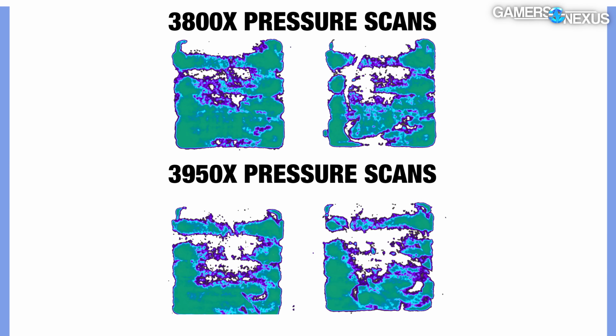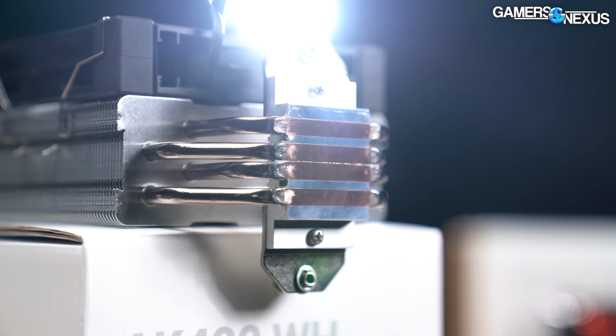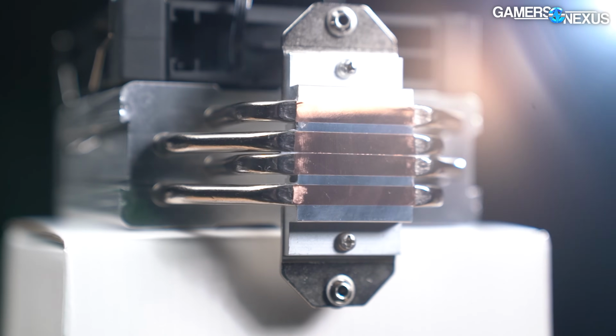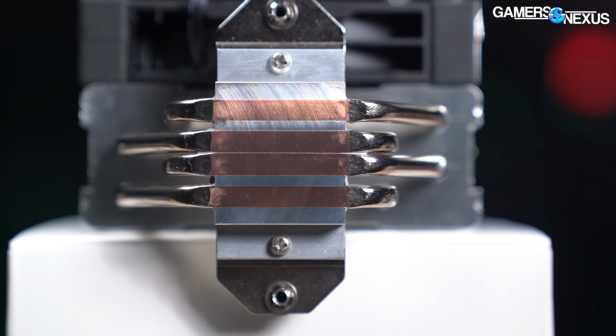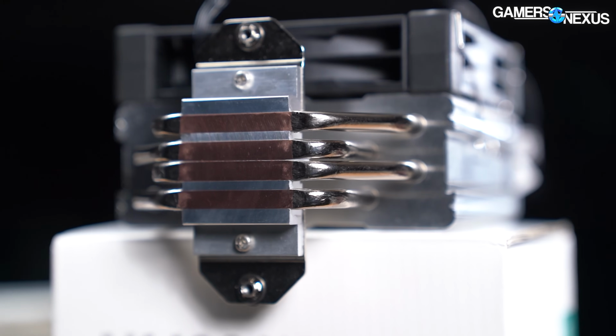And here comes that first test: the cold plate pressure scan. This test uses chemically reactive materials and a special NIST traceable scanner to measure the distribution of pressure across the CPU's IHS. This test evaluates the design of the cold plate and the mounting system, but mostly the mounting system, and how effectively they work together to hold the cold plate to the IHS.